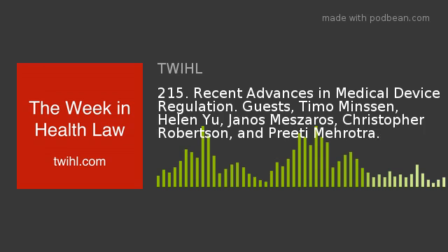Now, even though the MDR introduces this more nuanced classification system to increase regulatory scrutiny of devices, these classification levels apply only to active devices intended for diagnosis and monitoring. So again, it does not include the DHTs - they perform a monitoring function, but it's not intended by the manufacturer for diagnosis purposes. So it's very unclear whether these types of devices will actually fall within the regulatory scrutiny of the MDR. And even if they do, the classification system doesn't help with increased scrutiny.